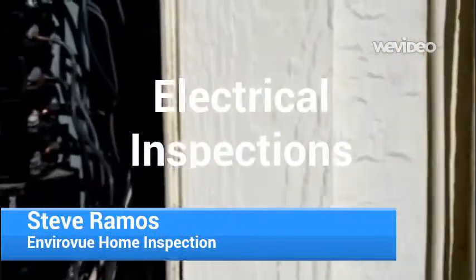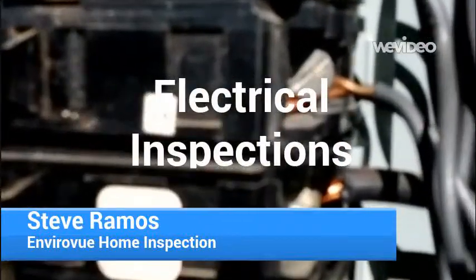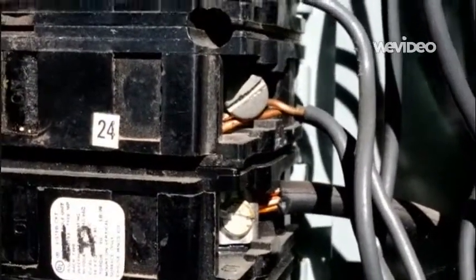More on electrical panels. One of the observations we often make is what we call two wires into one breaker, or double taps. As you can see here, there are two copper wires on that screw. This panel was not designed to accommodate two wires, and if you look real closely, that one bottom copper wire is actually not very tight at all. It's a very poor connection.